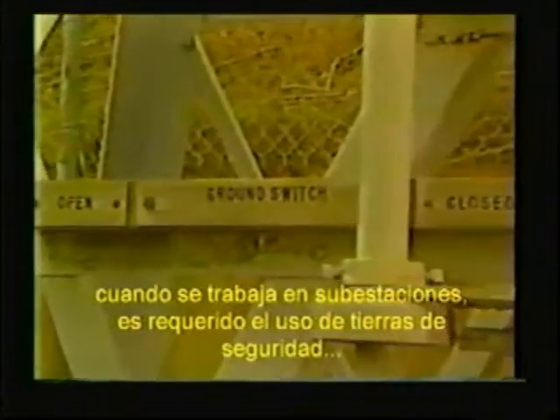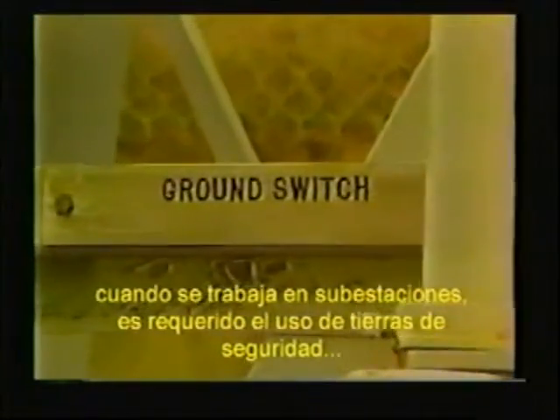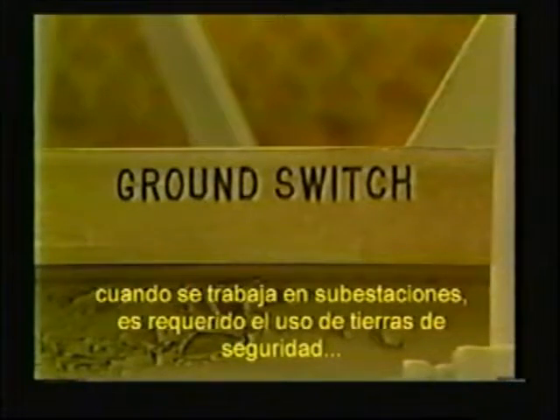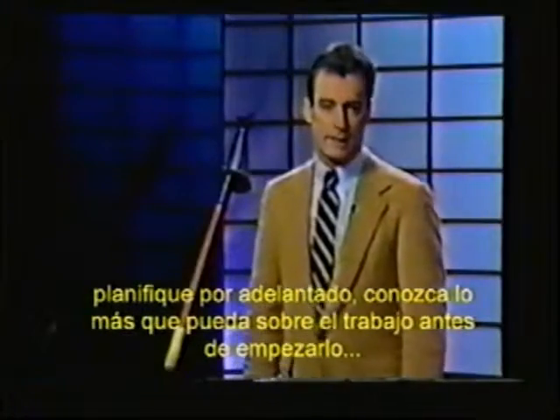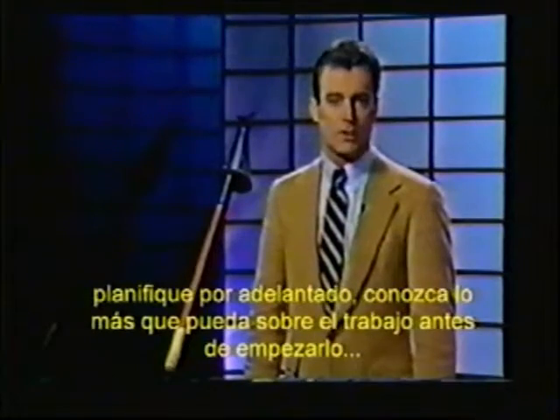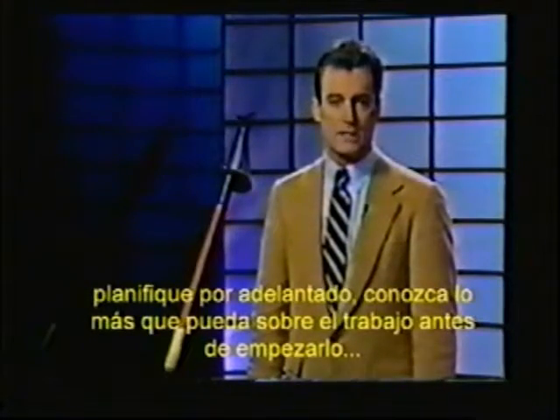When performing service on power equipment, the installed grounding switches or ground and test device should be used. If none are available, Dave brings portable grounding cables and a hot stick with him. And above all, plan ahead. Dave always learns as much as possible about each job before he starts.